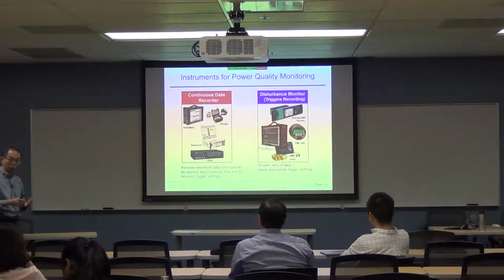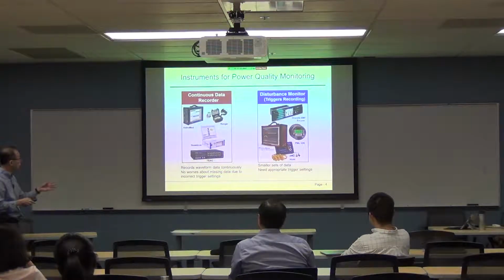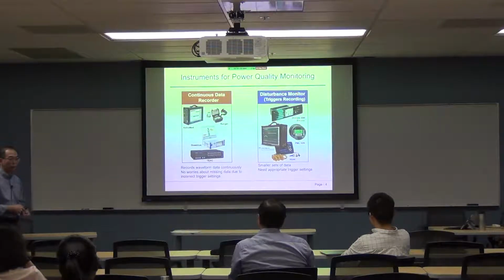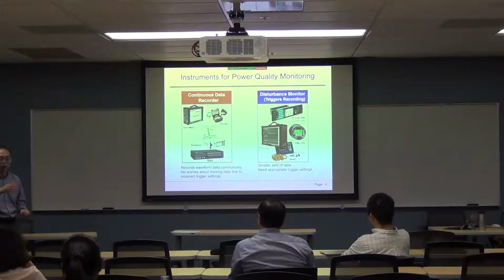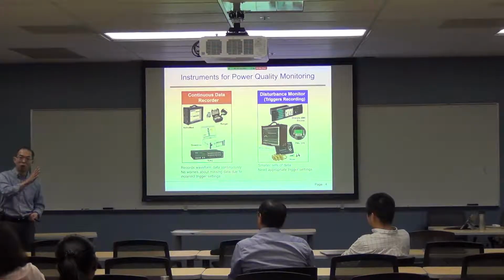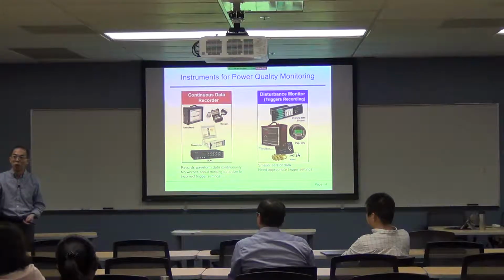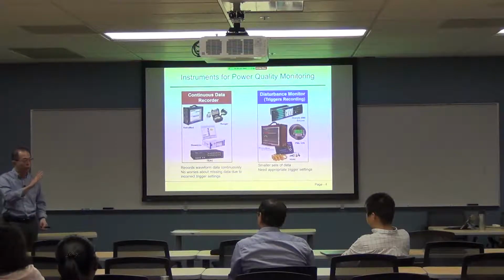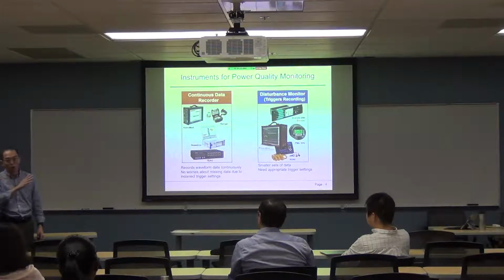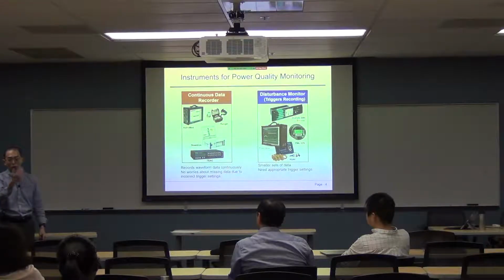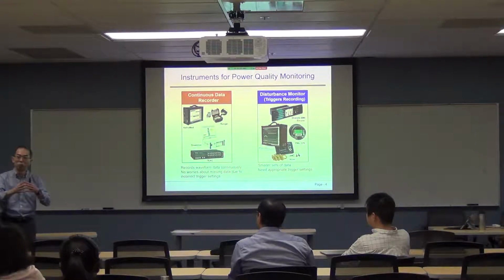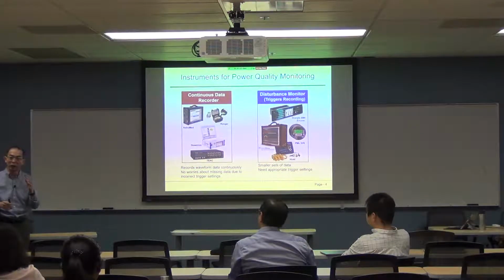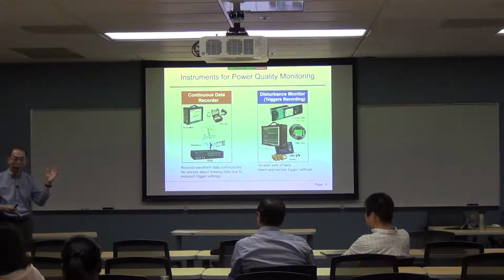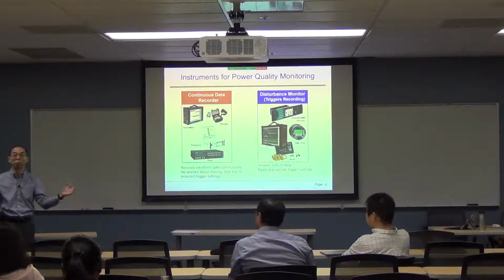Now there are 2 basic kinds. One is what we call the continuous data recorder - it will record waveforms or RMS values continuously, regardless of whether there is a disturbance on the line or not. It just keeps eating up all the waveforms that come around. So at the end, you end up with tons of data, so much data. The headache is that you have too much data, but the good thing is that it captures everything, good or bad, whether you want it or not.